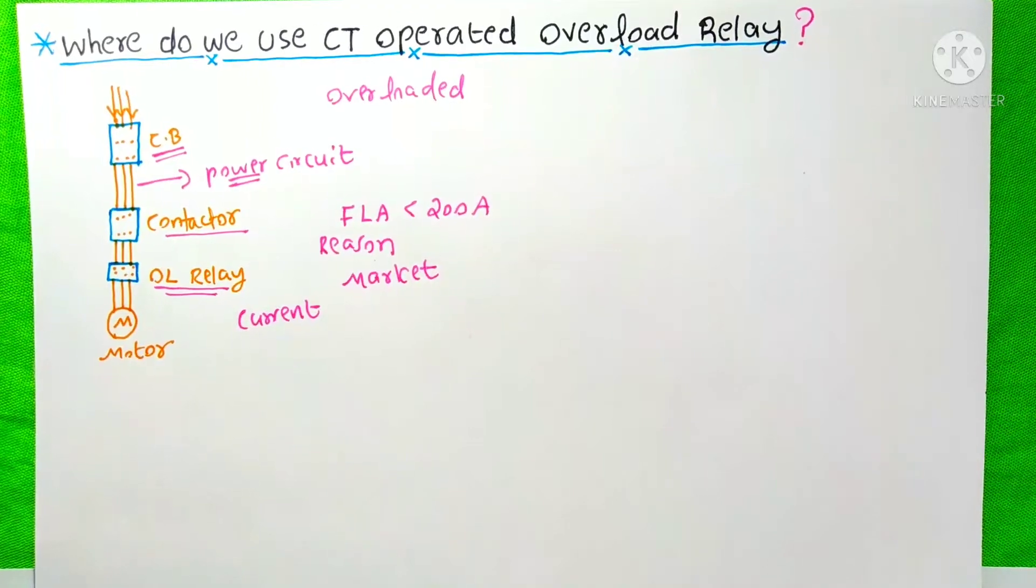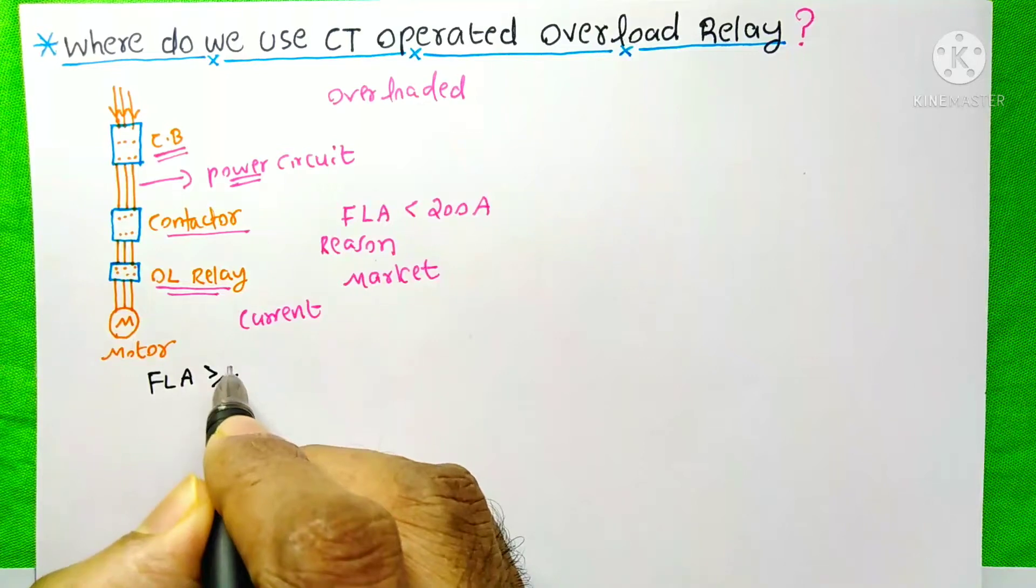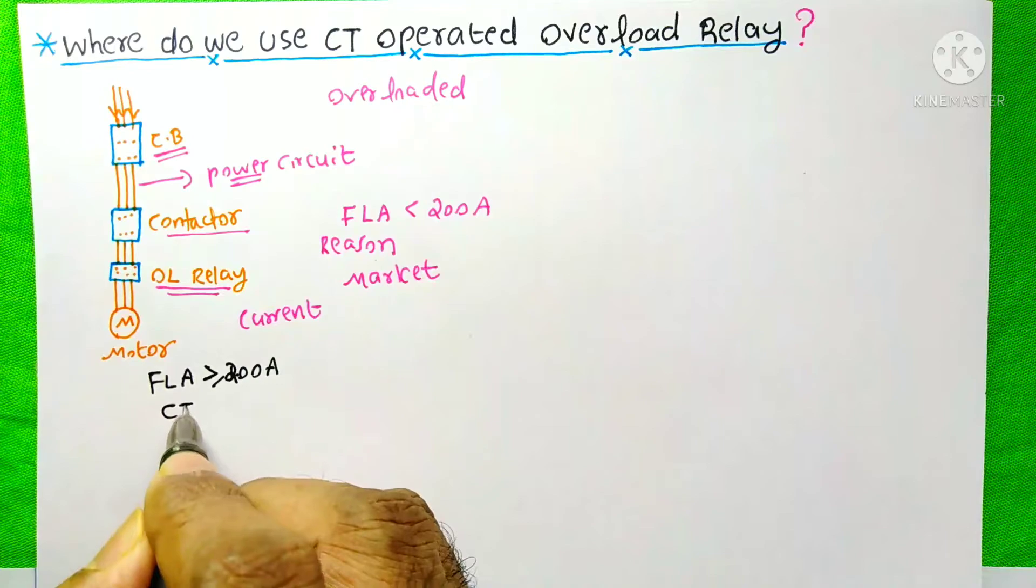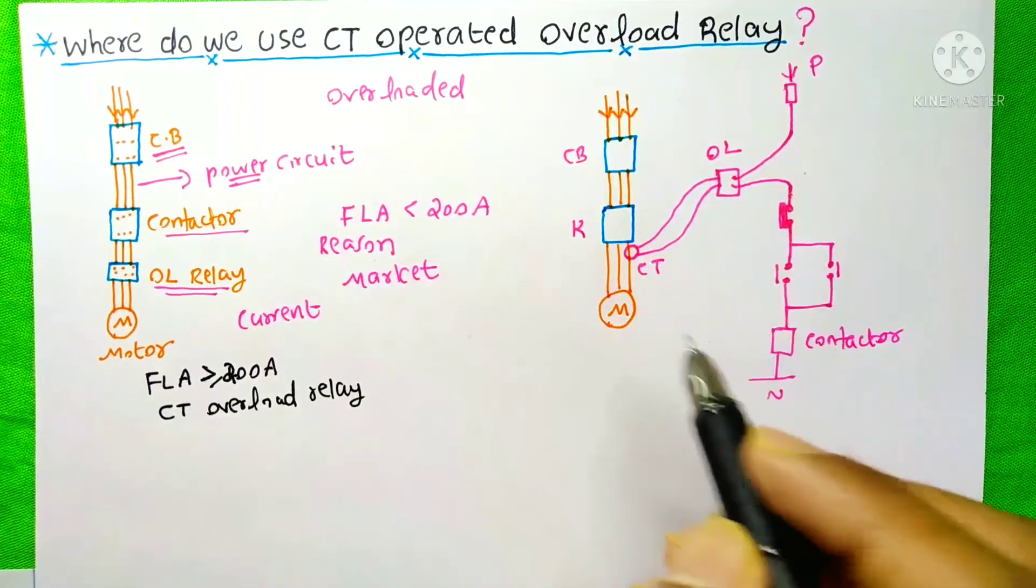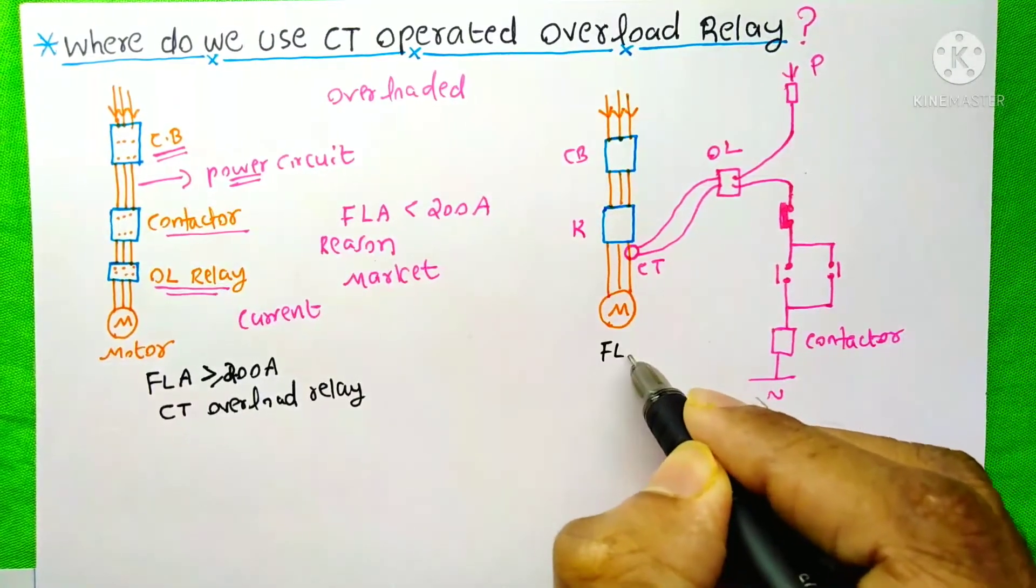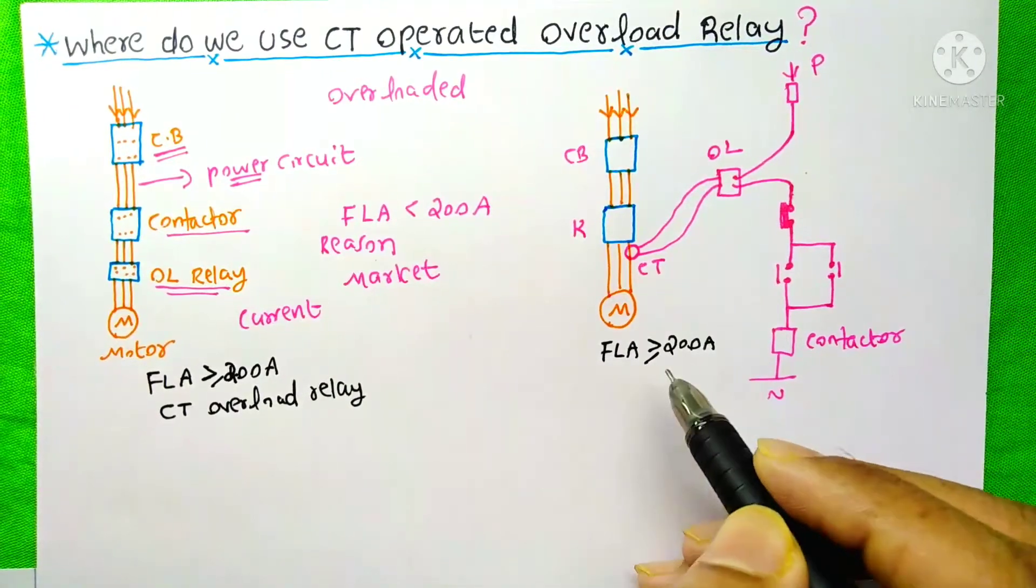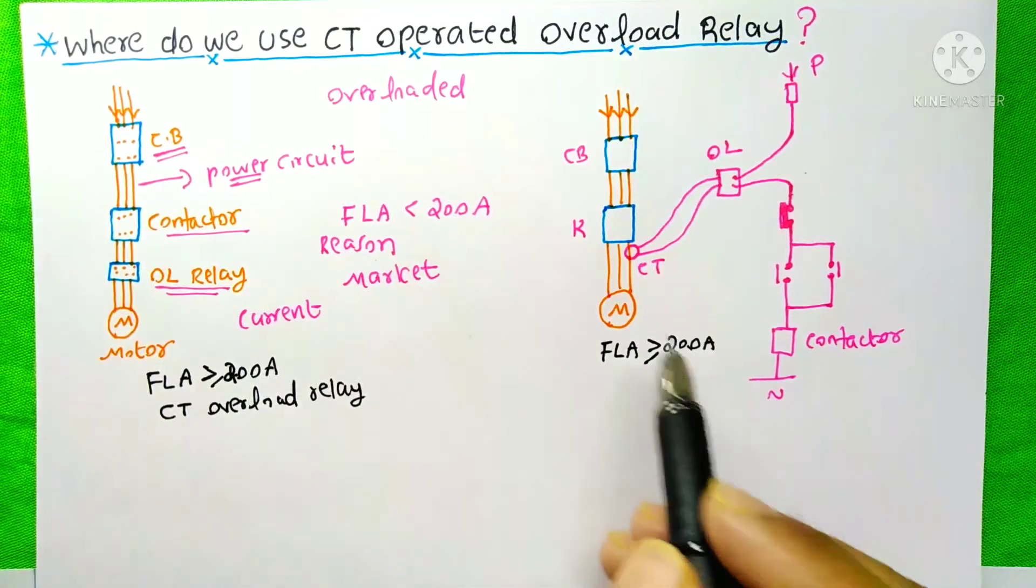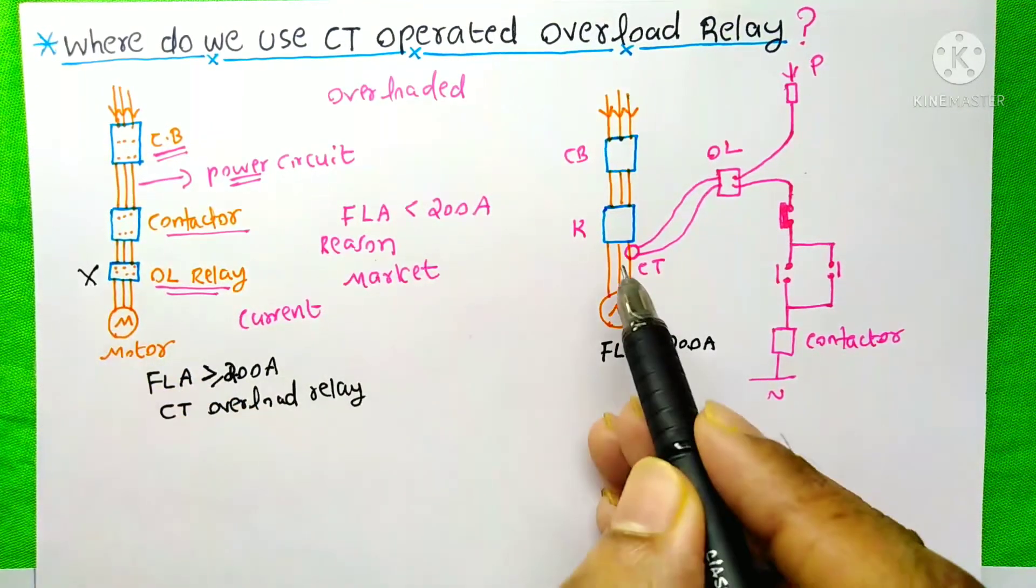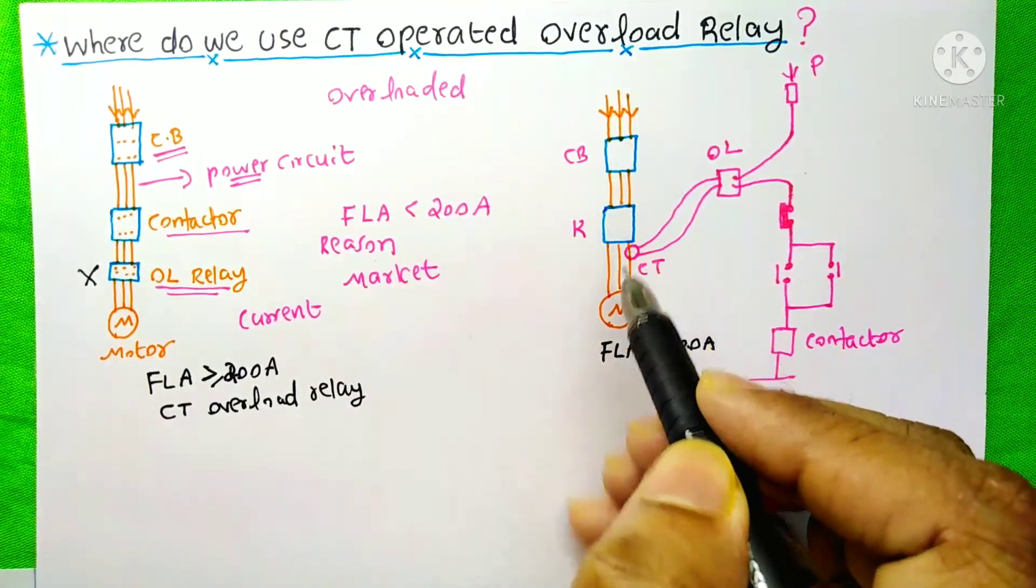Suppose our motor consumes the full load ampere greater than or equal to 200 ampere, we will not use this overload relay in the power circuit. In this case, see, here only circuit breaker and contactors are present on the power circuit.